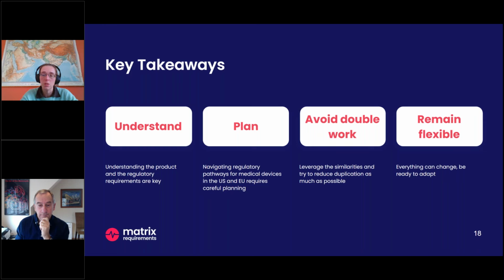Also, when we are talking about software with an AI component, you have already some standards that are focusing specifically on AI. For example, and now I have to really make sure that I say it correctly, the ISO 34971, which is a standard about implementing 14971, so risk management, for devices with machine learning. So there you have a standard that gives you guidance on how to apply ISO 14971 when you have an AI that is based on machine learning.